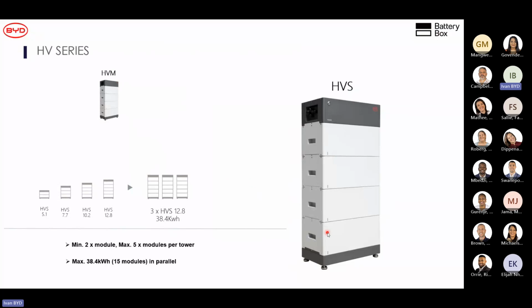So here we've got the HVS, which is a high voltage battery. The difference between high voltage and low voltage batteries is as you add modules to a high voltage battery, your voltage goes up. So that's different from a low voltage battery. I'm going to touch on that again. So your smallest battery bank that you can make with the HVS is 5.1 kilowatt hours, and you can go all the way up to 12.8 kilowatt hours in a single tower, and you can parallel 3 towers to make 38.4 kilowatt hours. You do have to have all the towers the same height, because the voltage in your tower is determined by the number of modules in your tower, and you have to make sure that all 3 towers have the same voltage.